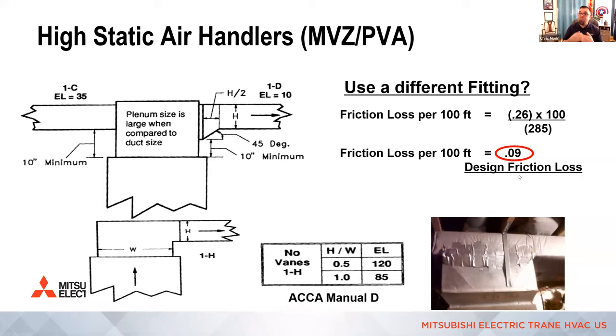Yes. Turning vanes, if done correctly, evenly spaced small vanes at the correct angle, will reduce equivalent length drastically. I actually had some slides on that, but I took them out. It really does get used a lot in commercial, especially on flat 90s. It does not get used very often correctly in residential applications, because instead of just using a right angle return drop in the return, let's say at 65 feet, you could put in evenly spaced small vanes to get the air to make a nice easy transition turn in that whole 90 and drop it to 20 feet. Or you just have an internal radius and drop it to 30 feet. It's not a huge difference in that example.